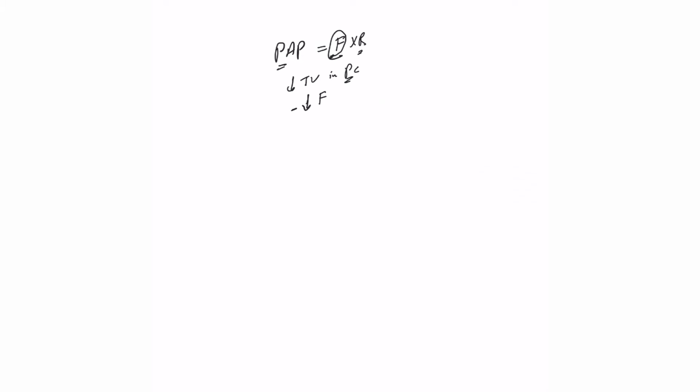We don't have direct control on the resistance, but we do have direct control on the proximal airway pressure, which in pressure control mode is the inspiratory pressure. So simply by decreasing this, you can decrease the flow. Also, the other way that decides how much tidal volume we get is the inspiratory time: how much time we are receiving this flow at this rate. The smaller the time, the smaller the volume. So two ways here to decrease tidal volume in pressure control mode.